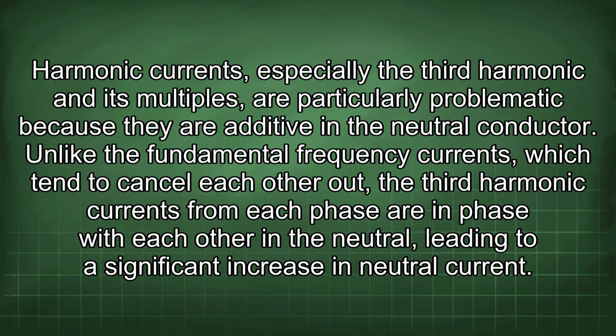Harmonic currents, especially the third harmonic and its multiples, are particularly problematic because they are additive in the neutral conductor. Unlike the fundamental frequency currents, which tend to cancel each other out, the third harmonic currents from each phase are in phase with each other in the neutral, leading to a significant increase in neutral current.